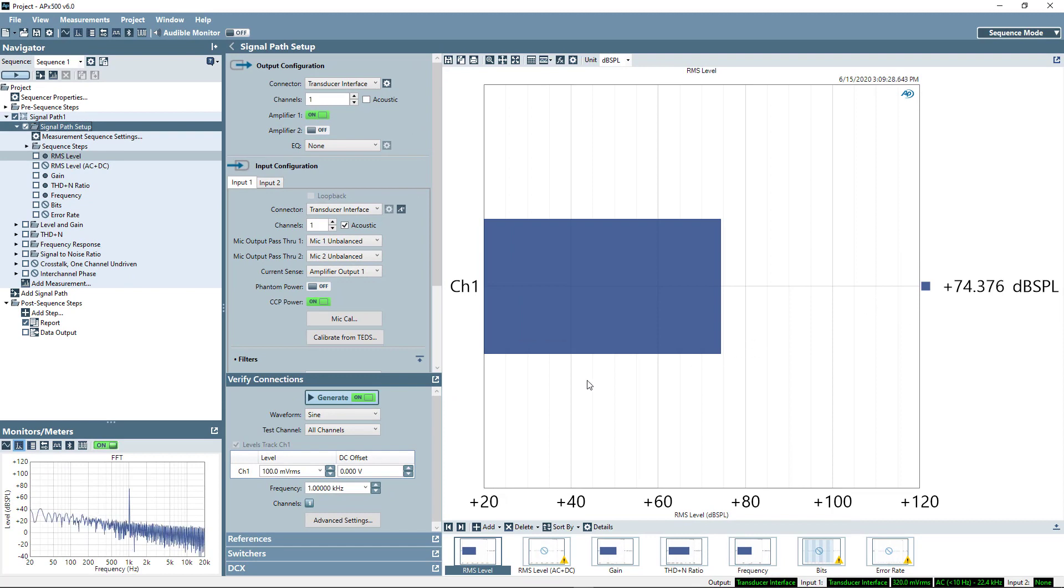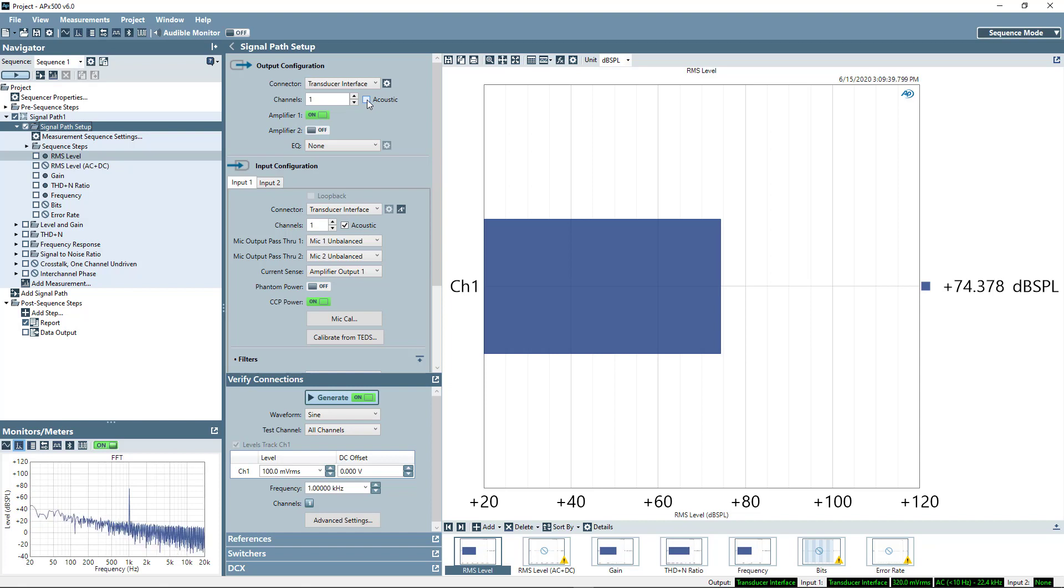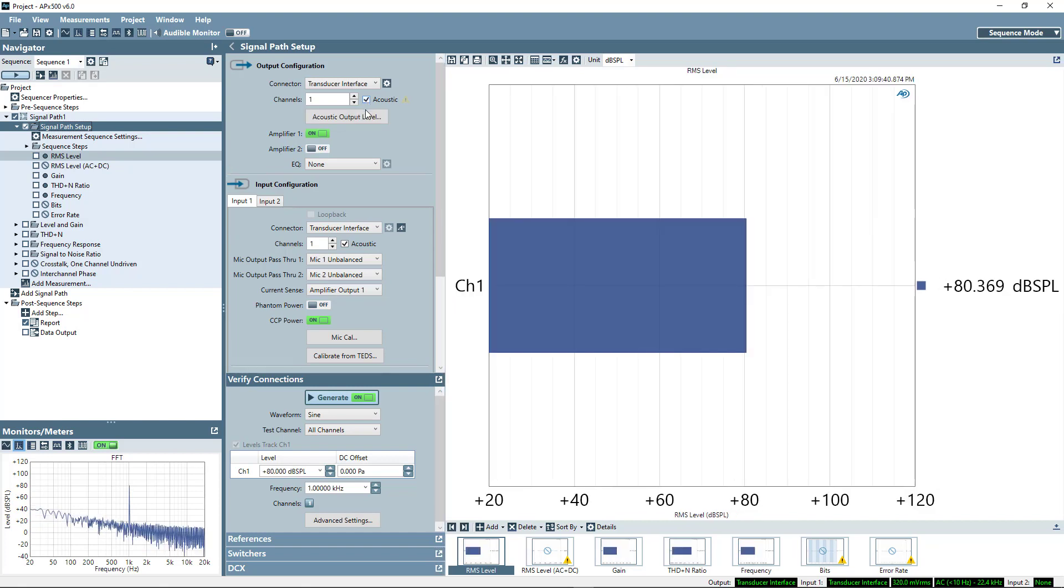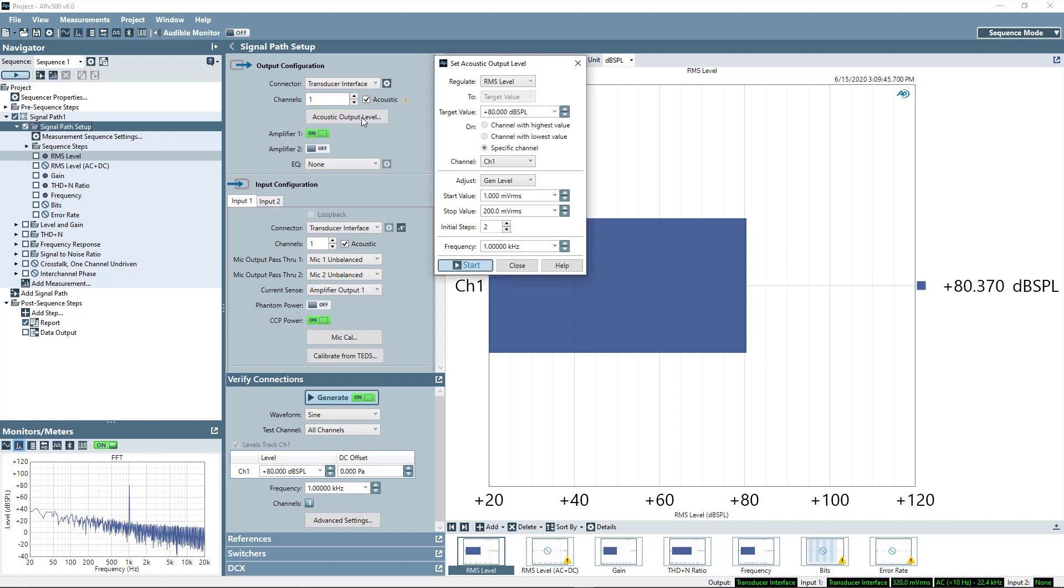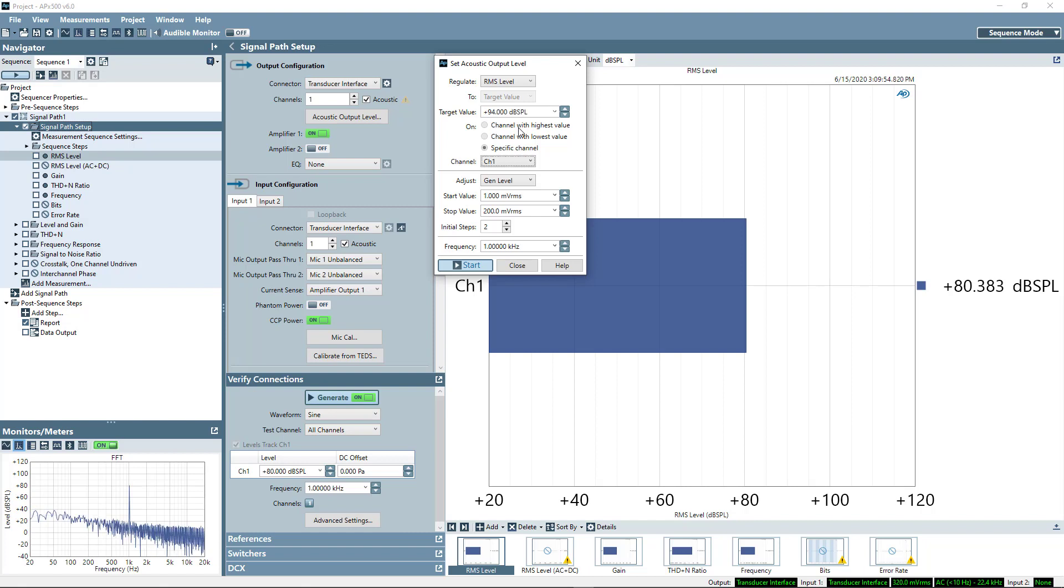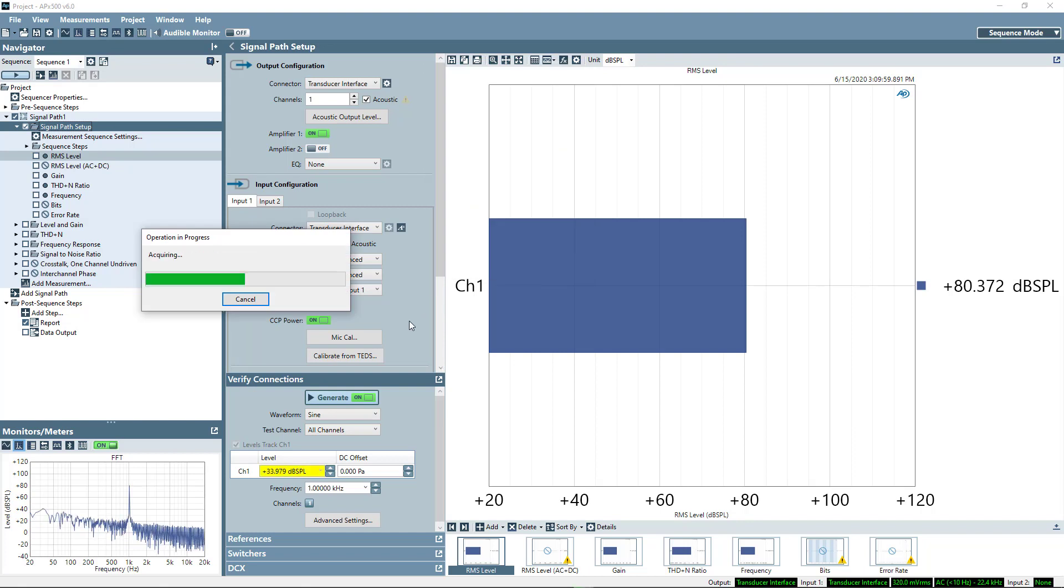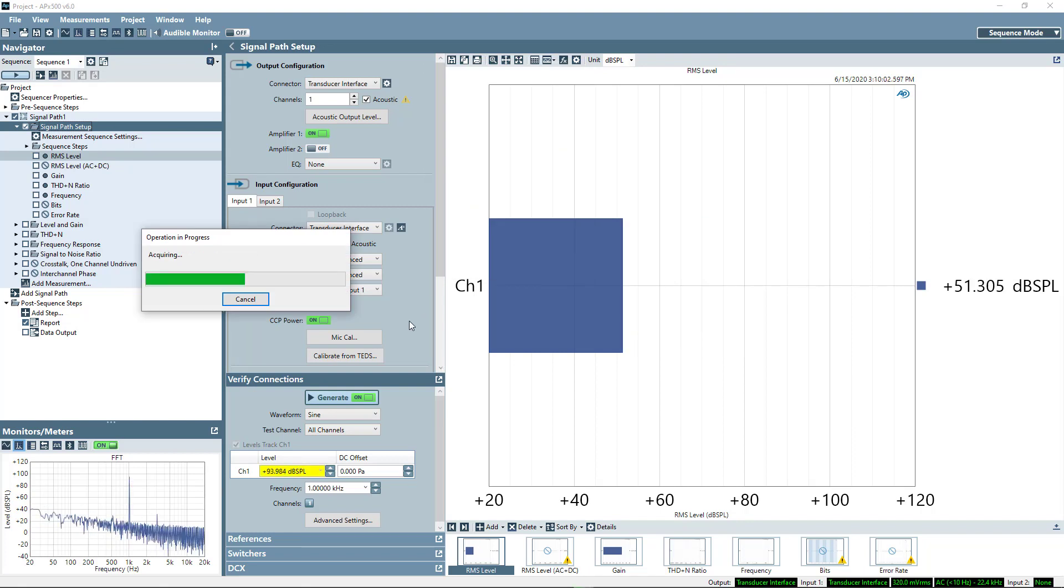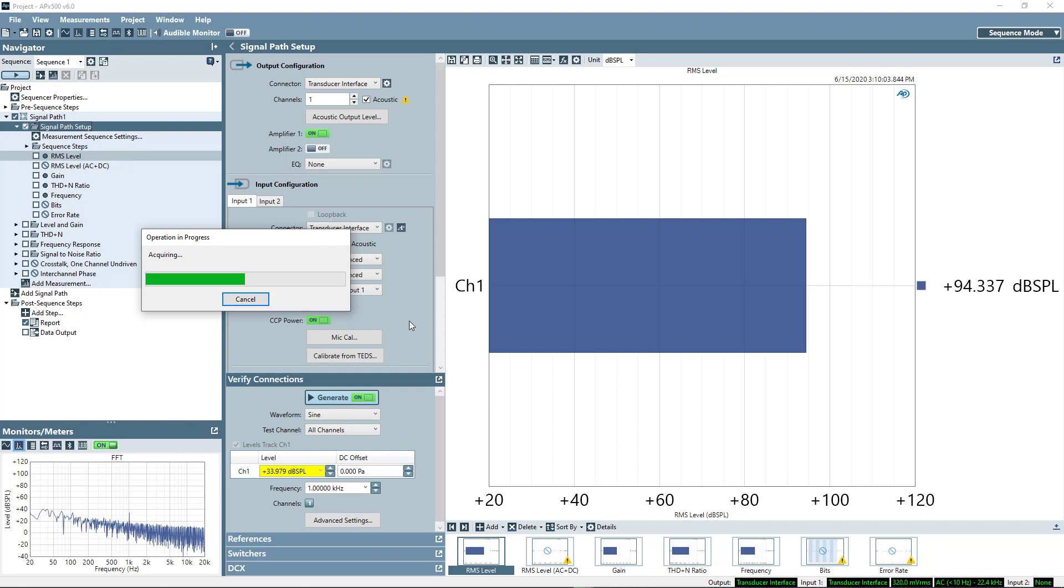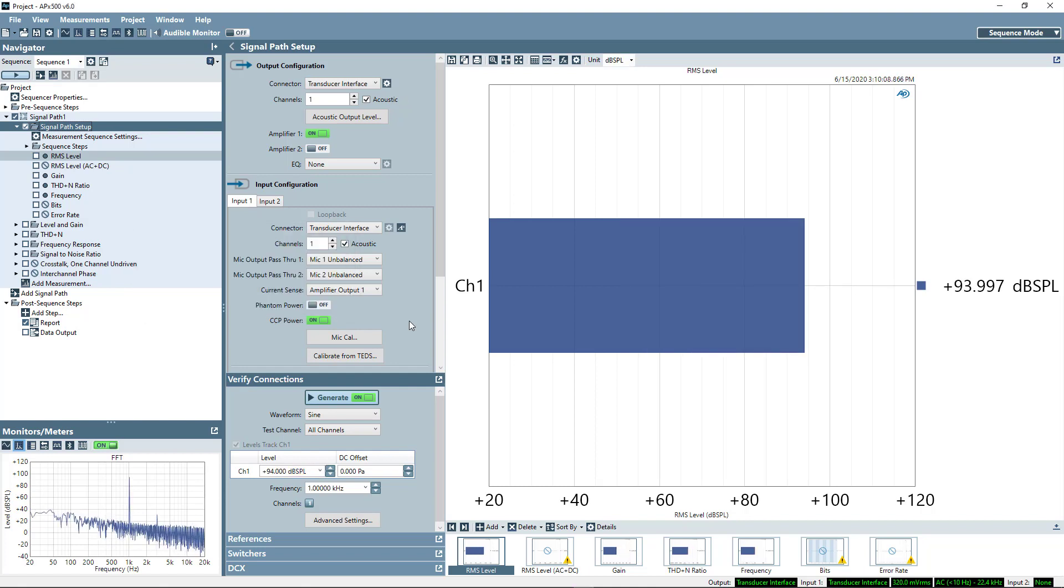Now, since I'm measuring a microphone, what I want to do is calibrate my output. So now I'll go back to the output side, and I'll go ahead and select acoustic output, and I'm going to select this acoustic output level button, which will bring me to our set acoustic output level dialog, and I'll say I want to set a target of 94 dB SPL, and I'll put in a healthy stop value, and now the system is going to automatically vary the level of the analog generator until it finds the output that gives me 94 dB SPL, or just about 1 Pascal of sound pressure.